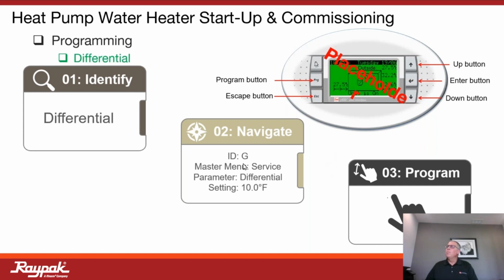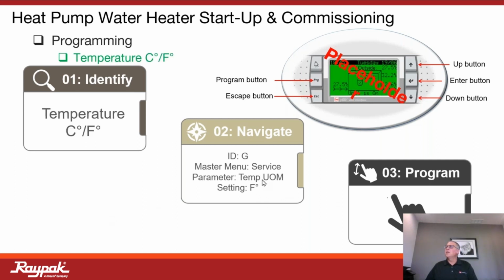Again, with the differential, we're navigating to that G menu, dropping down to the service menu, the adjustable parameter of differential. You hit enter, and then the setting will populate itself, and then we hit that up and down arrow. We can make that whatever we want. Then we hit the enter button again to accept it, and then hit the escape. Very easy to program these units. Here's unit of measure. We can also do unit of measure for pressure as well.